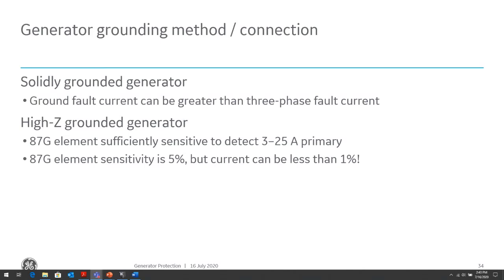So in that case, if you have a solidly grounded generator, and this can be mostly for sacrificial generators, low-cost generators, those generators are more sacrificial to the system because of that high level of fault current. If you do have a ground fault, the chances are you're going to permanently damage that generator and need to replace it. So this is always in the economics of scale here too.